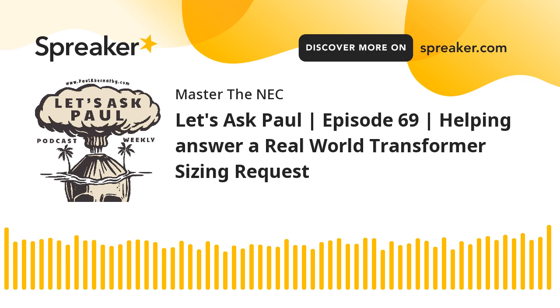So this tells me the HVAC equipment has a nameplate that says minimum circuit ampacity 78 amps. The maximum overcurrent protection is 100 amps. So no different than your normal HVAC application. Gotcha. The only thing we're doing is installing a transformer to make sure it can handle this load. That's it. Don't overcomplicate it. That's all we're doing for it, if that's what this person is doing. Sounds like that's what they're doing.